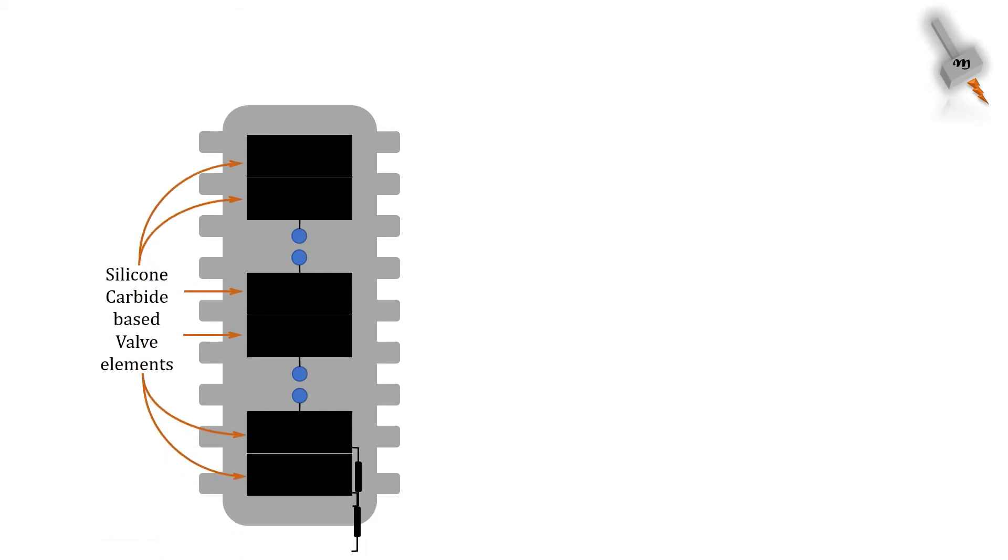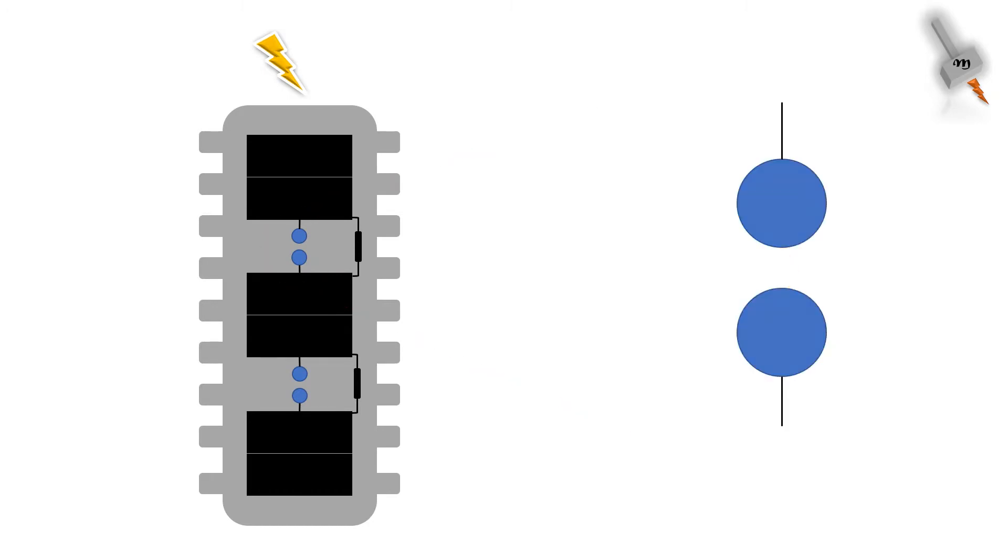Historically, gap design was used in silicon carbide design of lightning arrester. But due to the challenges faced in limiting the follow-on current, those designs of lightning arrester are currently not in use. A follow-on current is an undesirable condition where the lightning arrester with a spark gap successfully diverts a lightning surge to the ground but then is unable to return to the normal high impedance state after the abnormal transient event ends.